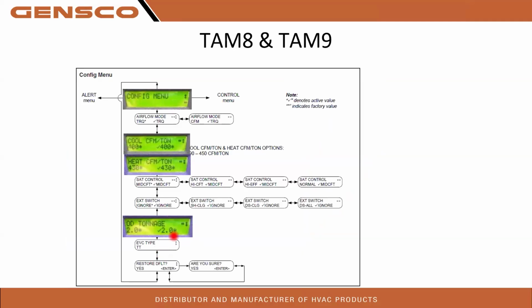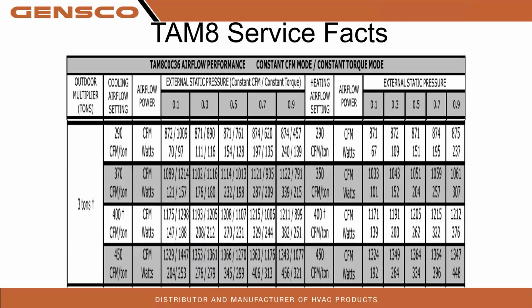You're always going to put in your outdoor tonnage. If it's not communicating in a 24-volt system, we have to plug in that outdoor tonnage. TAM 8 service facts, again, same stuff that we've been seeing, right? So you're going to see this constant same graph. I think we went through enough of them. There are settings in here for the constant CFM mode or constant torque mode. Again, constant torque mode is going to get you higher wattage to achieve that CFM.